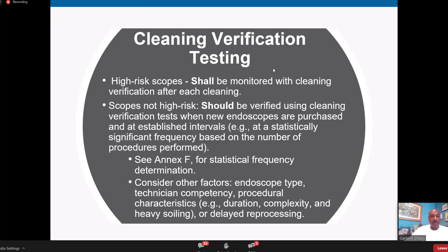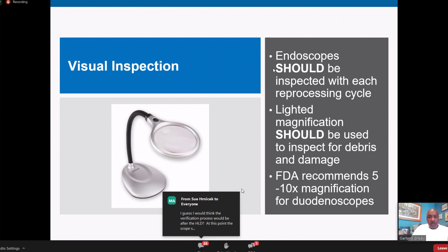Visual inspection. Again, endoscopes should be inspected with each reprocessing cycle. Lighted magnification should be used for inspection for debris and damage. FDA recommends 5 to 10 times magnification for duodenoscopes. In some of our areas, the lighting is poor, and it's due to old buildings and things like that. Even in my area, we have been upgrading and doing more to get this lighted magnification, and it's done a world of good for staff. Some of these scopes are very small. Some of them are large enough that you can see, but with our imperfect eyes, even with glasses at times, we still can't see. So if you do not have it, get lighted magnification in your area. Next.